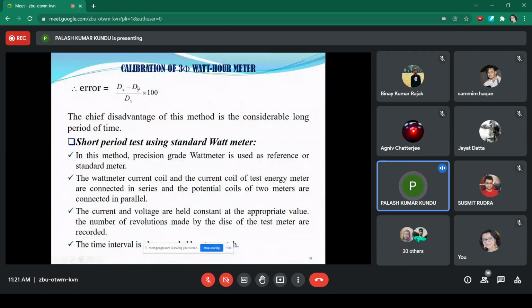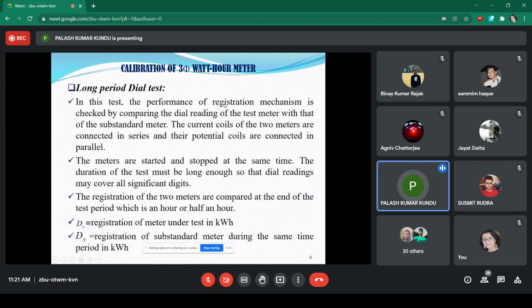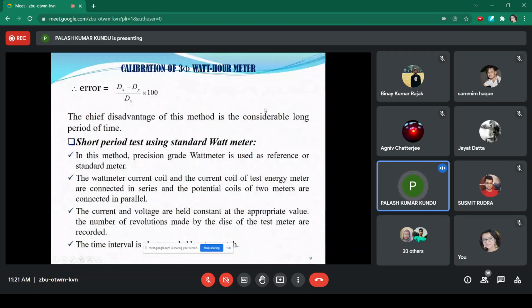So dx and dy are the meter readings of the test meter as well as the substandard meter. But the time required for the long period dial test is much longer. So that is a disadvantage. The user has to wait at least 30 minutes according to the standard.